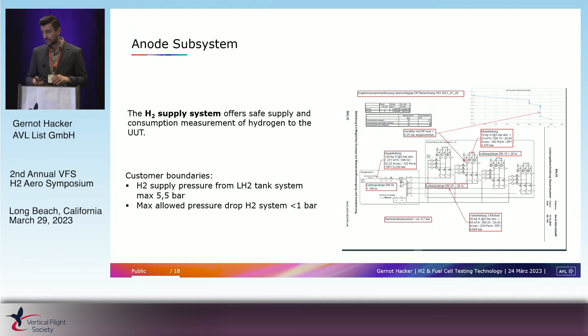The hydrogen supply, how does it look like? There is the liquid hydrogen tank, where you can deliver via trailers to this buffer or storage tank. From there the liquid hydrogen is transmitted to the testing tank system, where you have the test tank, then the evaporator, and then you go to the fuel cell system testbed. The task of this testbed is the handling, refueling, and optimization of the tank as such. In total, the hydrogen flow rate that can be handled there is up to 120 kilogram per hour.